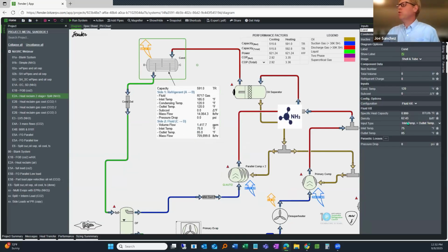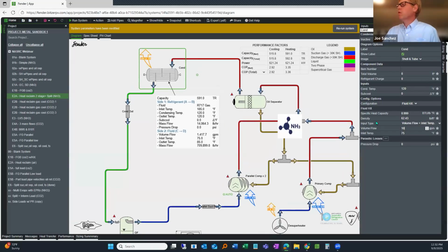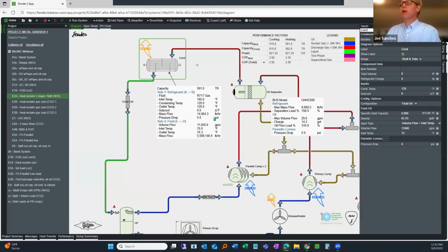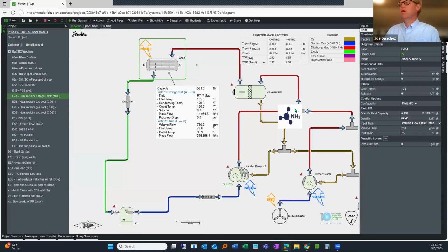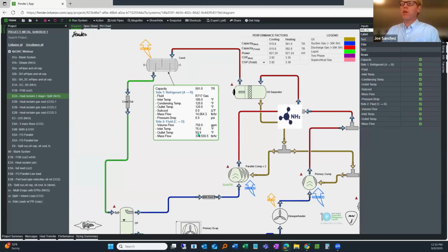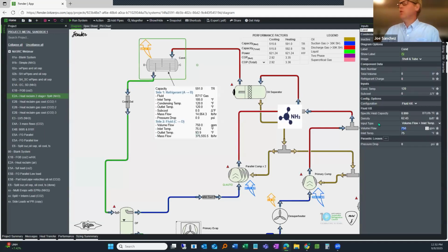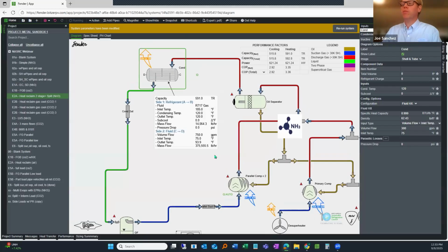So like I said, if you're an end user and maybe you wanted to see what happens when you reduce the flow rate. So I've got, sorry, that was way too much, 750 gallons per minute. 750 gallons per minute creates 94-degree water. And you could reduce that even further and see the implication.